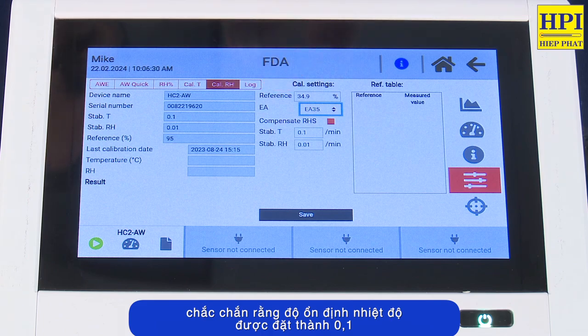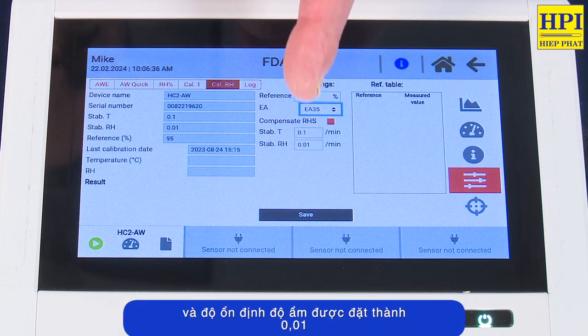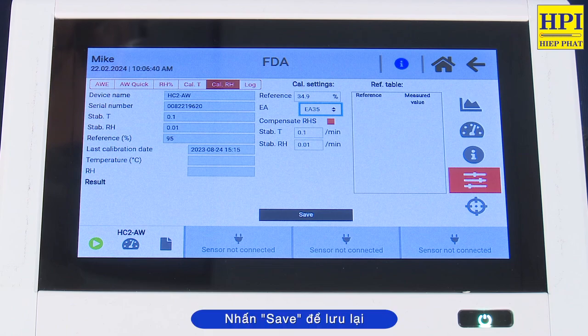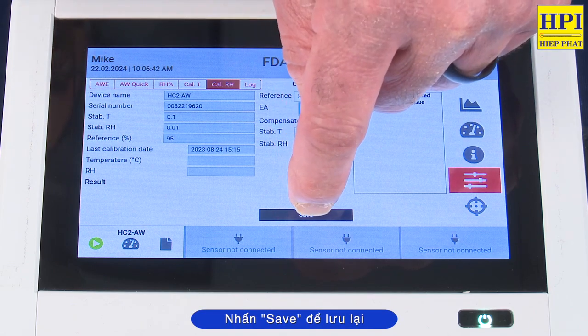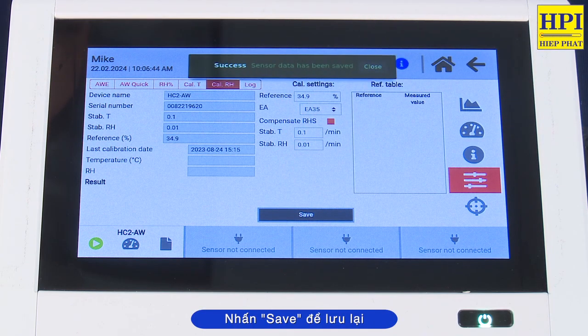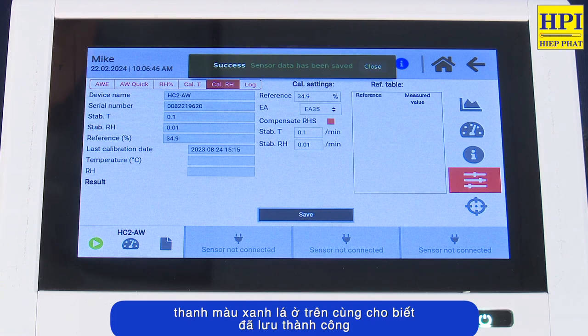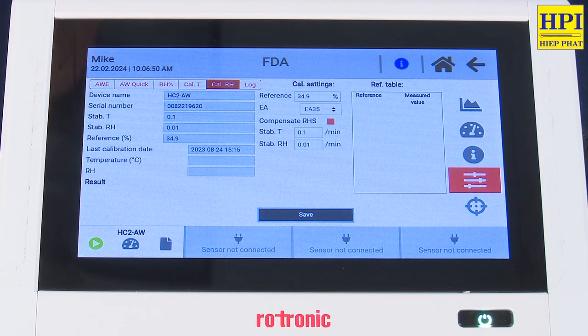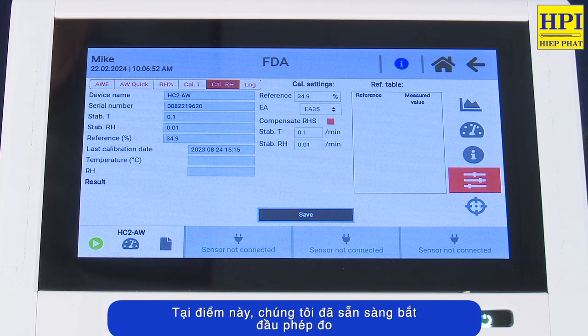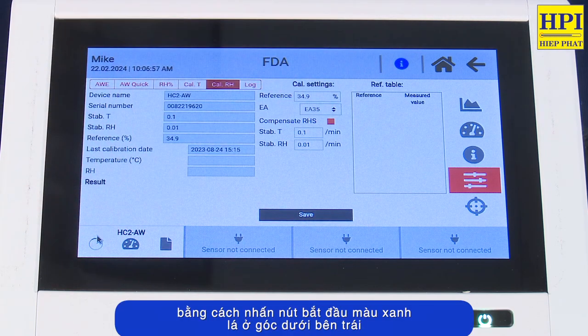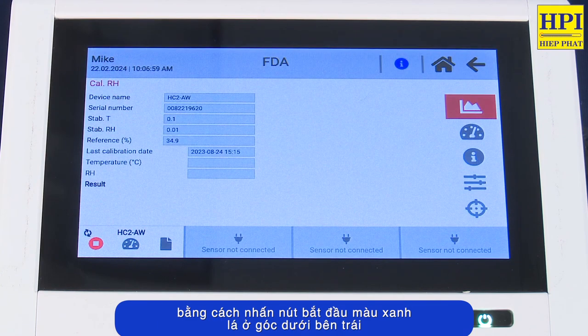You want to be sure that the stability temperature is set to 0.1 and the humidity stability is set to 0.01. Once we've made these selections, we want to save. Green bar at the top indicates we've successfully saved these settings. And at this point, we are now ready to begin the measurement. We can do that by pressing the green Start button in the bottom left-hand corner.